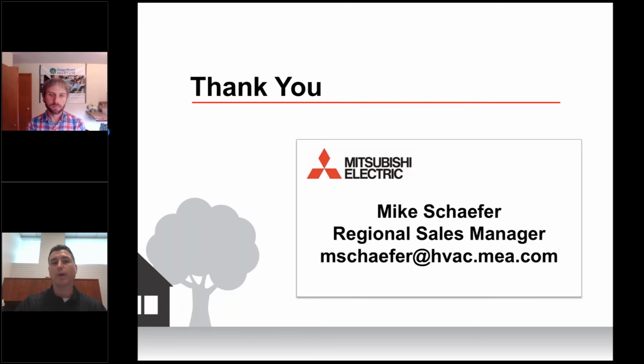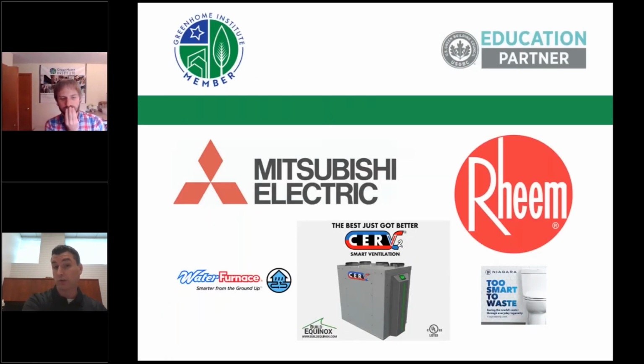Where you get into, especially with high performance construction, right? We're green, so we talk about lower load things and higher performance construction. I actually recommend supplemental dehumidification or a system like the CERV that also does supplemental dehumidification when you get into shoulder season applications or low loads where you may have a latent cooling need and not a sensible cooling need. So our systems are air conditioners, right? So it's only going to run if there's a call for cooling. It's not going to dehumidify when there's no call for cooling. So if you get a day where you have a low load, but you still need a dehumidifier, that's where a supplemental one comes in. Yes, they do dehumidify. I glossed over the cooling when we're talking about these.